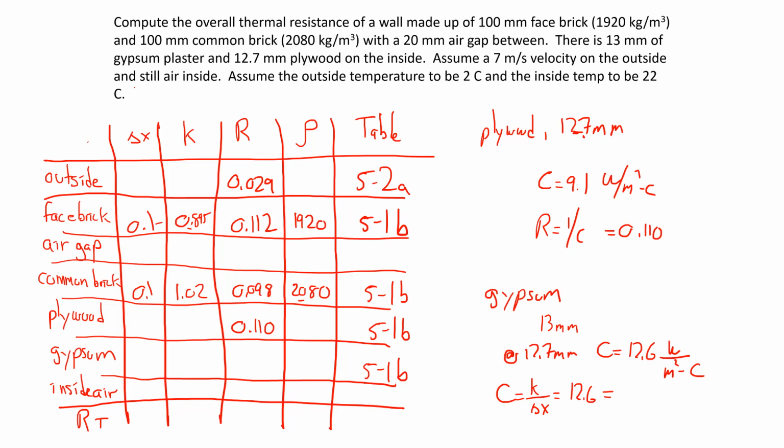The next is looking at the temperature difference. The delta T across it is about 20 degrees, right? Take 22 minus 2, you get 20 degrees. So in terms of the fourth column where it looks at temperature difference, the closest to that is going to be 16.7 degrees. So in the table, a mean temperature of 10 degrees and a temperature difference of 16.7.